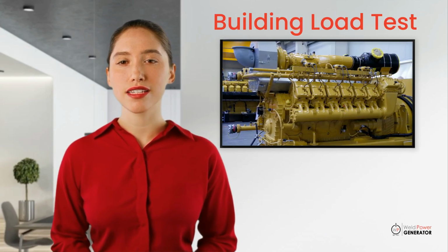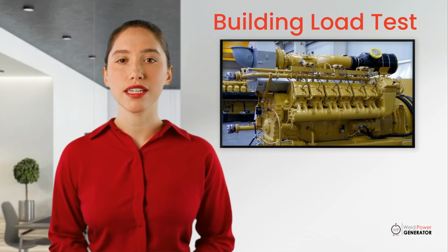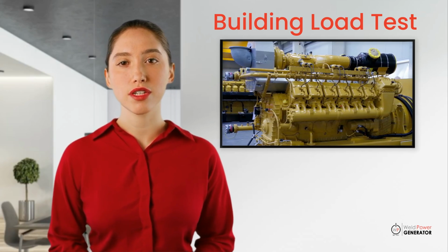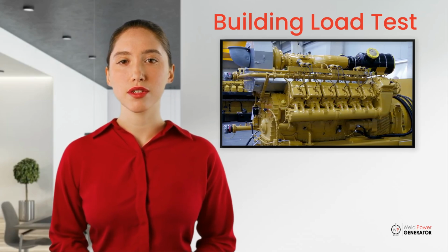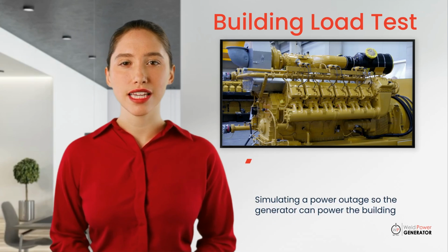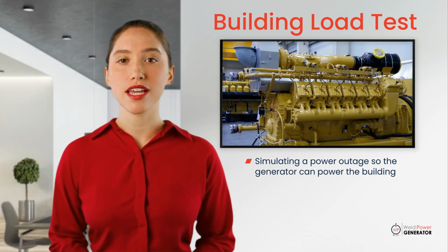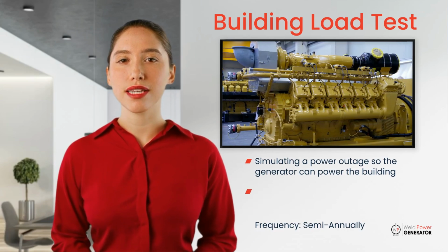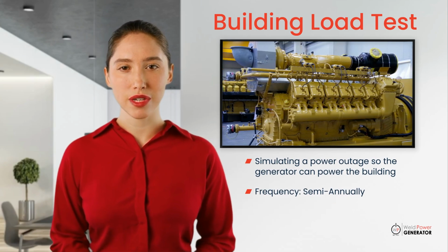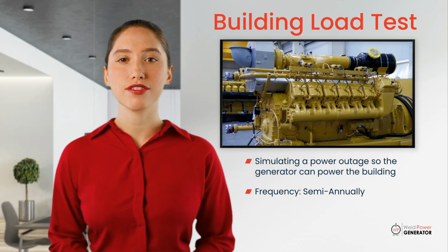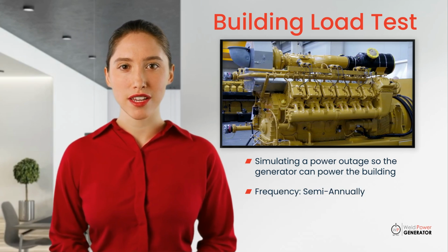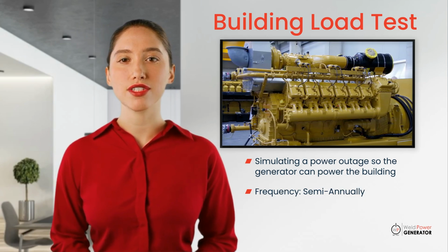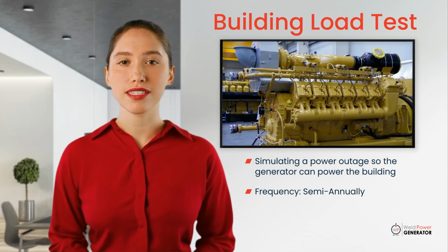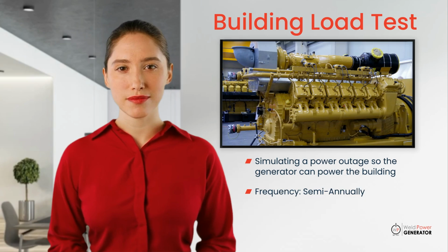A building load test evaluates the generator's ability to handle the actual electrical load of the building. This is performed under real conditions, simulating an outage to ensure the generator can meet demand. It's recommended to conduct this test semi-annually, and especially after significant electrical changes to the building. Building load testing provides assurance that the generator will perform as needed during a power outage.